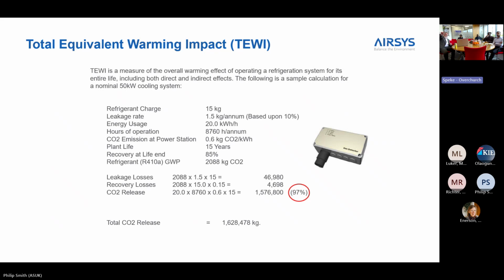What that says there, 97%, is the CO2 impact of physically running the unit. So the fact that it's got refrigerant in it only accounts for 3% of the CO2 that may be generated by that unit through its life cycle. Now, I say may because if it's installed properly, it's pressure tested properly, you may have zero leakage across a 20-year life. So whether you're using a unit with a GWP of 2000 or a GWP of 1, if it doesn't release, it has zero impact on the environment.